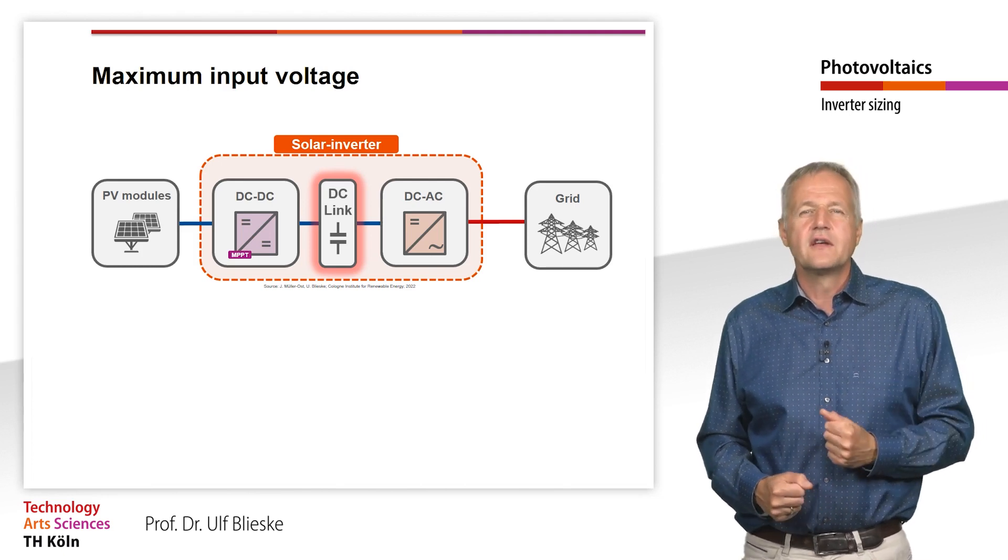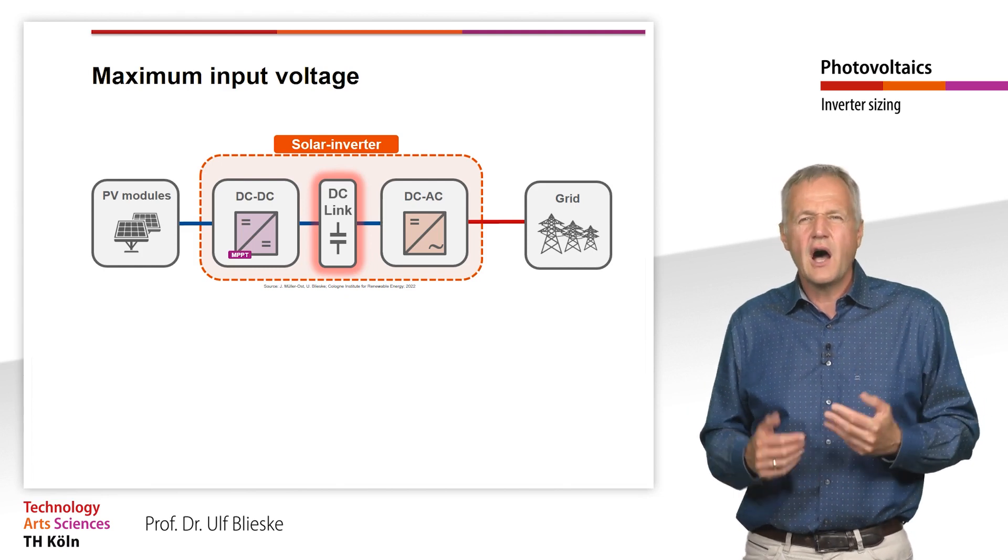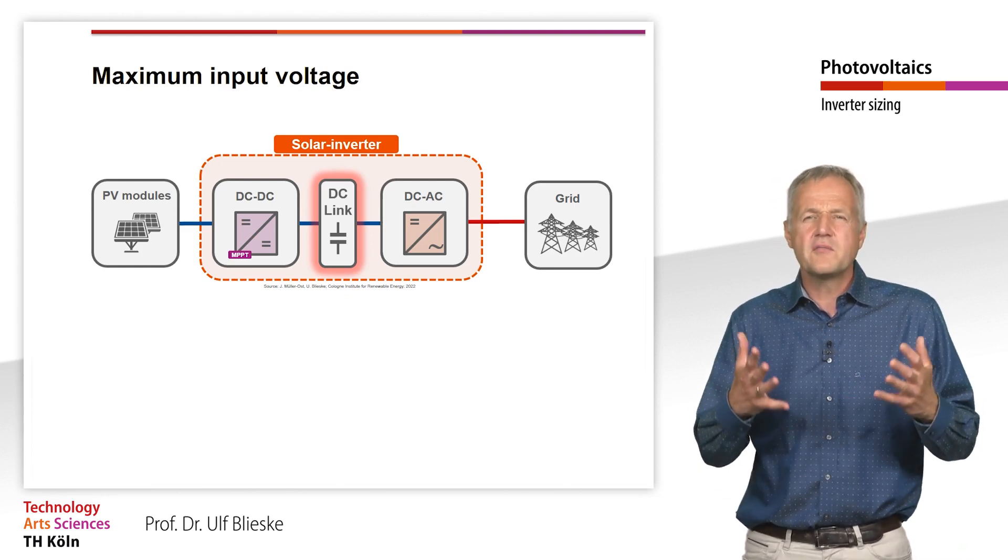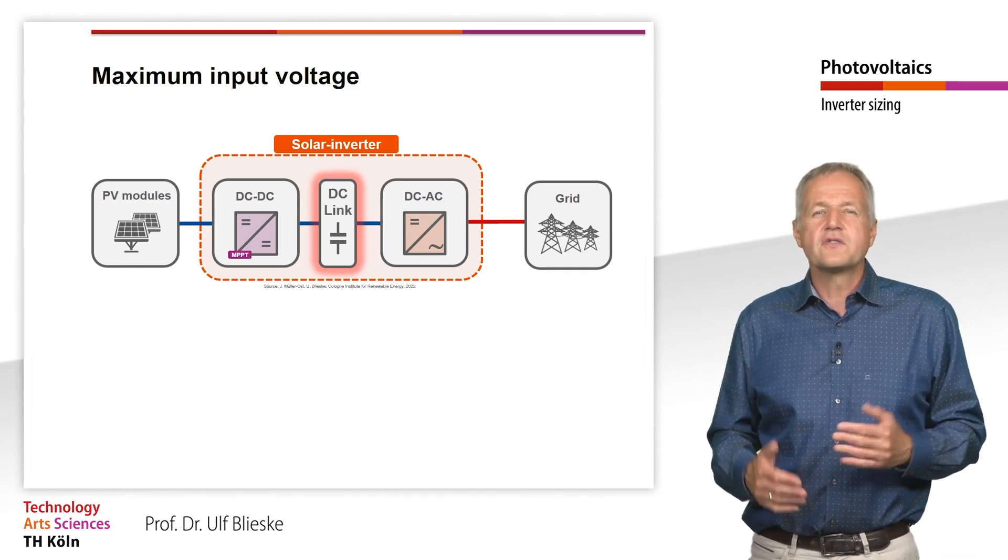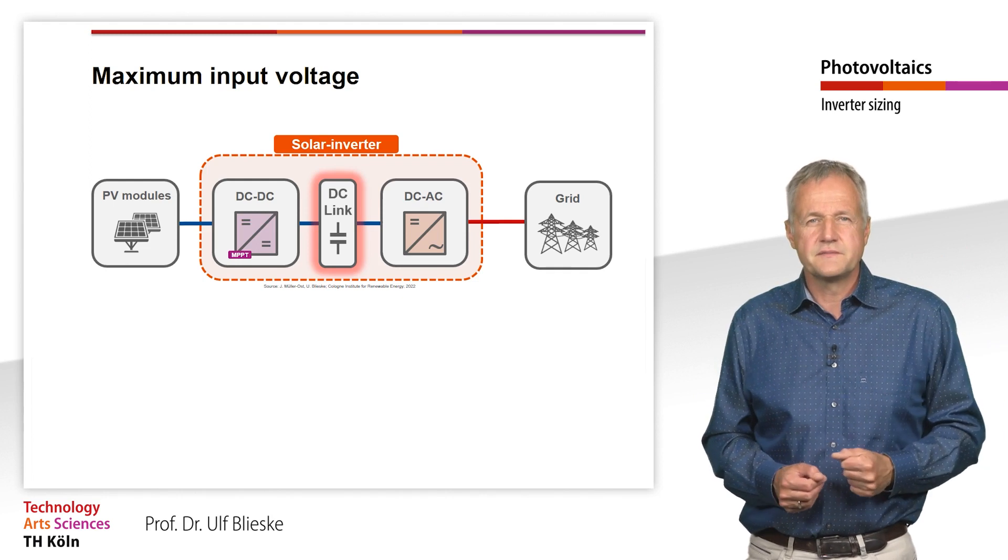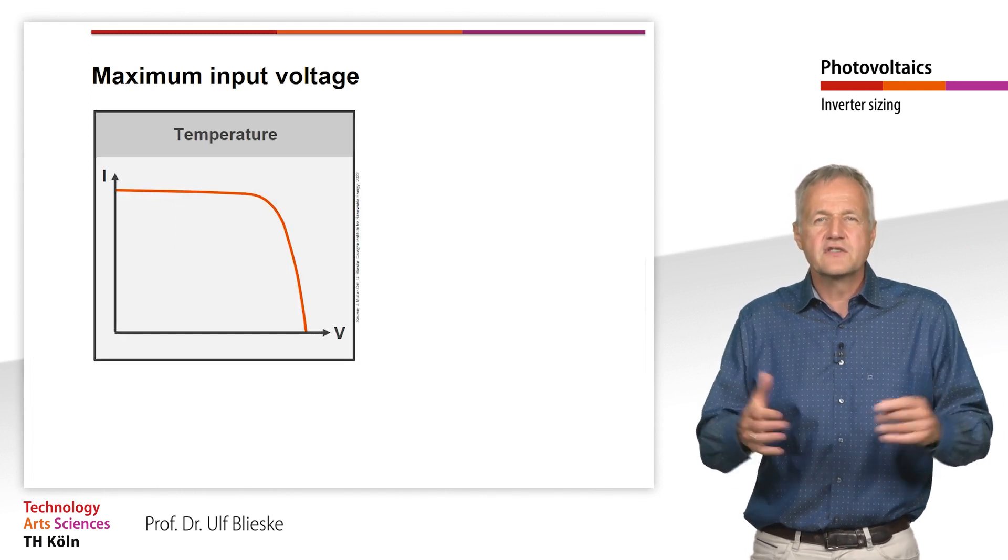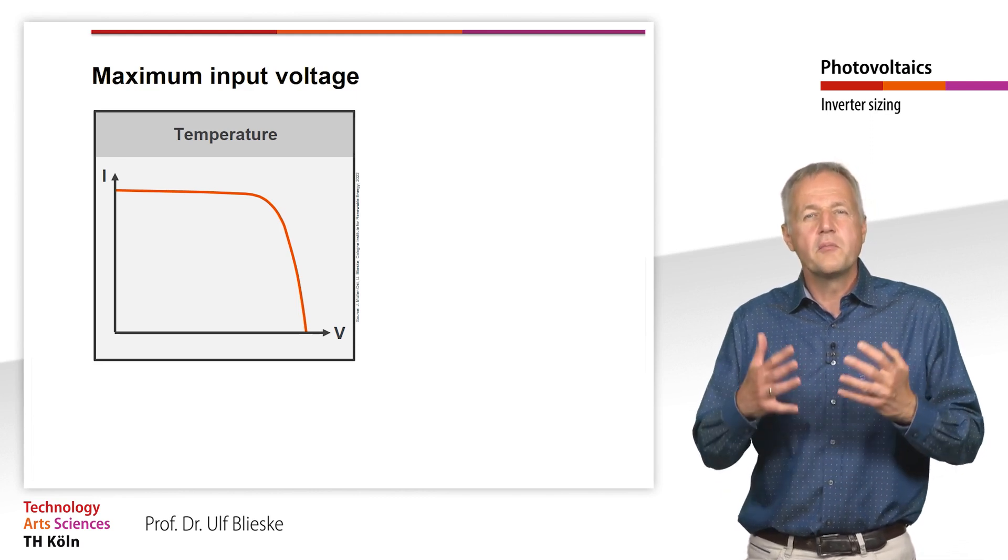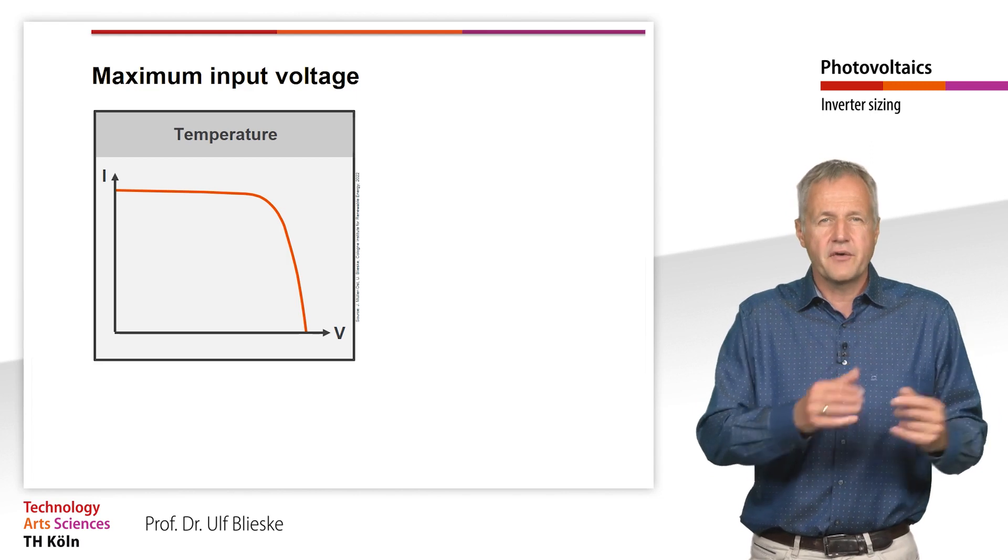Of course, the remaining power electronics of the inverter are also designed for a certain maximum voltage and these components are also destroyed if the voltage is exceeded. We must therefore ask ourselves under which circumstances the maximum possible DC voltage occurs at the solar generator.